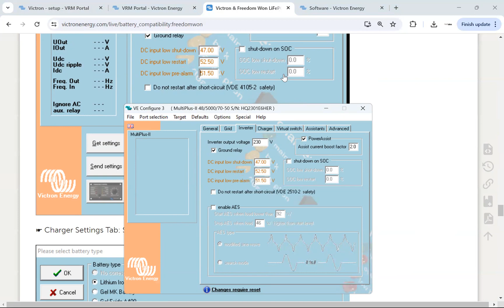Basically, you're just going to go through, and I can shift this down a bit so we can scroll up. 52.5, 51.5. So we'll go 52.5, 51.5. Very easy. Just follow through this programming. Okay. Now you'll notice there's a bit of a difference here. See here in the web page, we've got get settings and send settings. This is if you're actually connected through a laptop direct to the inverter on site. This is not what we're doing now. That little side pane does not have any data in it at all. So that means that we're working on this file remotely.